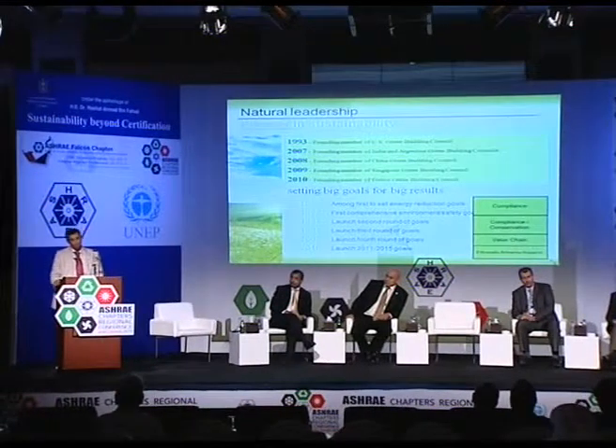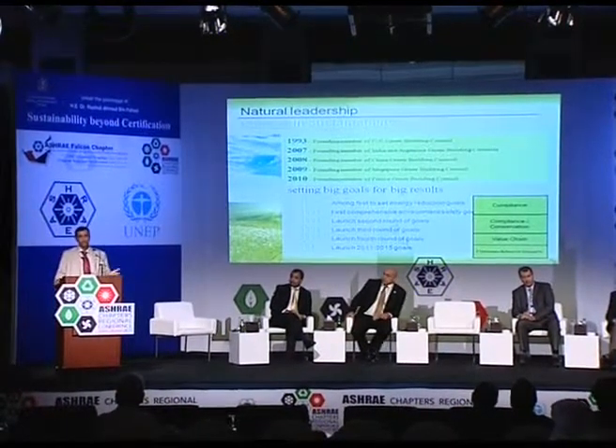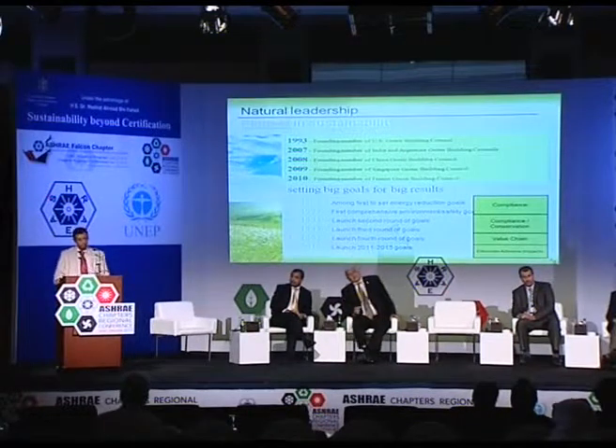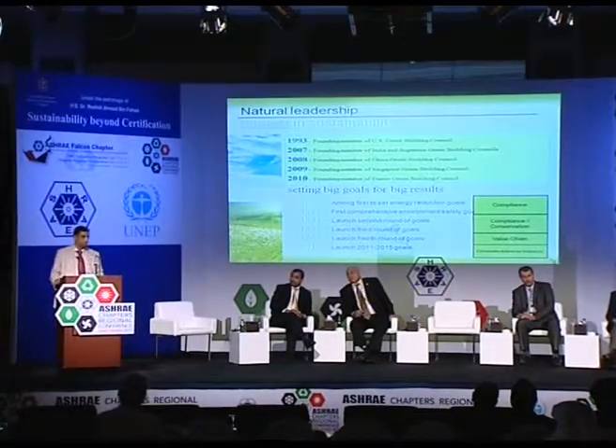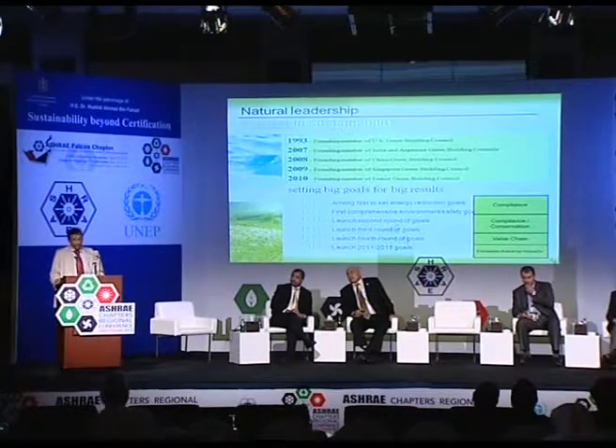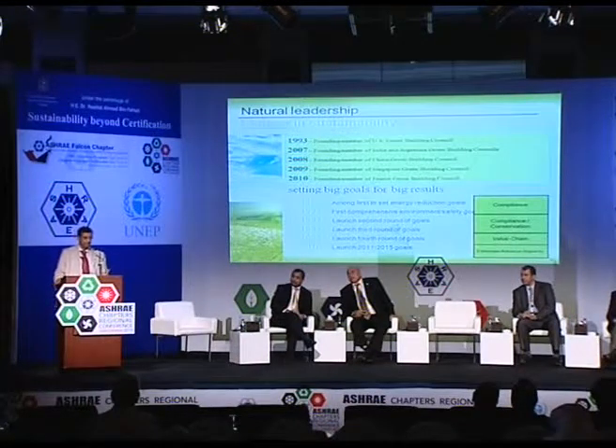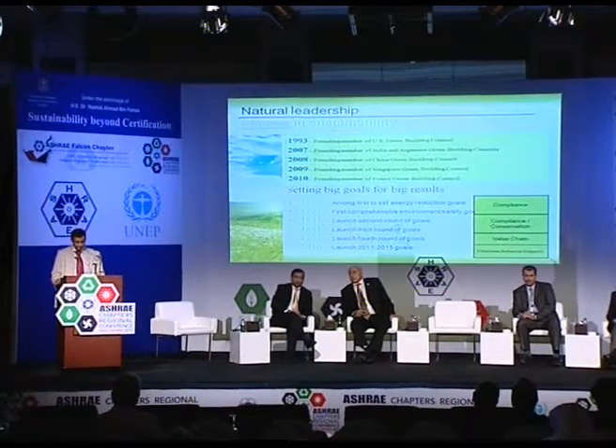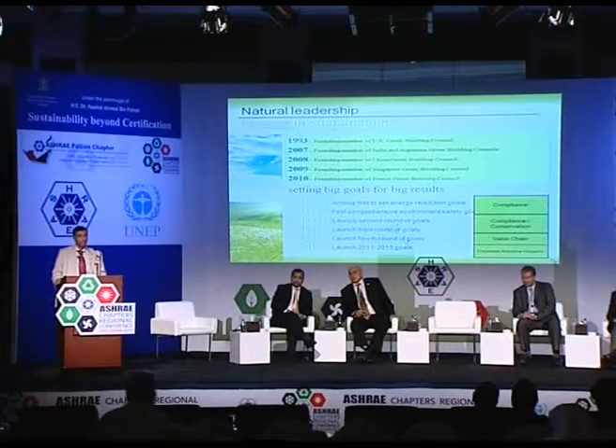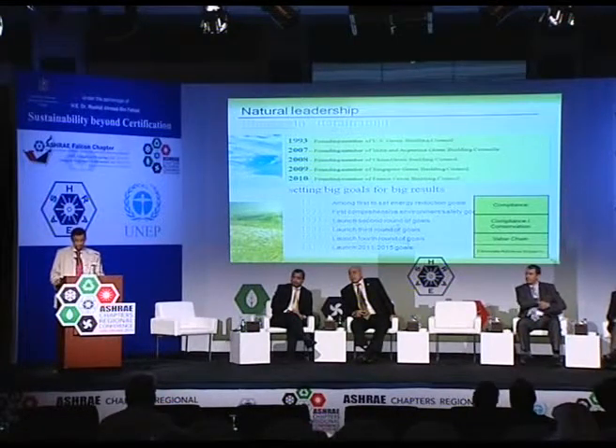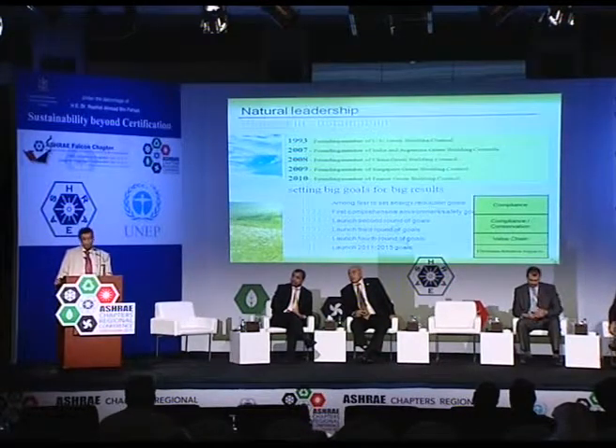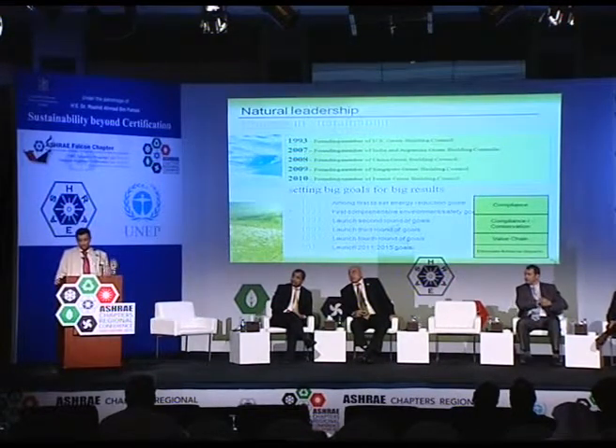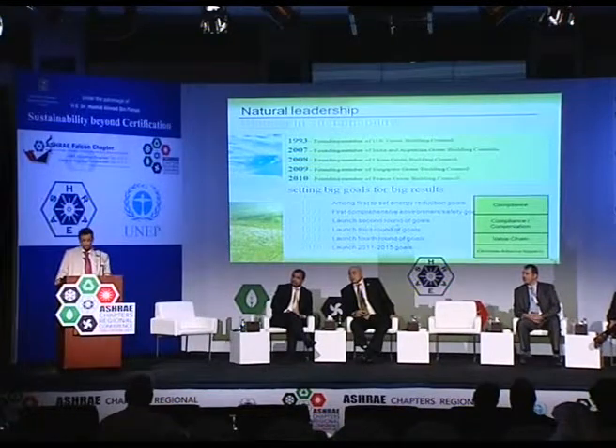Now, regarding what came out of this ASHRAE conference in Kuwait and the observations we noted as Carrier: the ASHRAE method of measuring efficiency is EER, based on net capacity, which fully accounts for system integral losses as well as fan and motor inefficiencies. The kilowatt-per-ton rating method used by some Gulf countries, especially Kuwait, is based on gross capacity and doesn't fully account for system inefficiencies. That's our first observation.